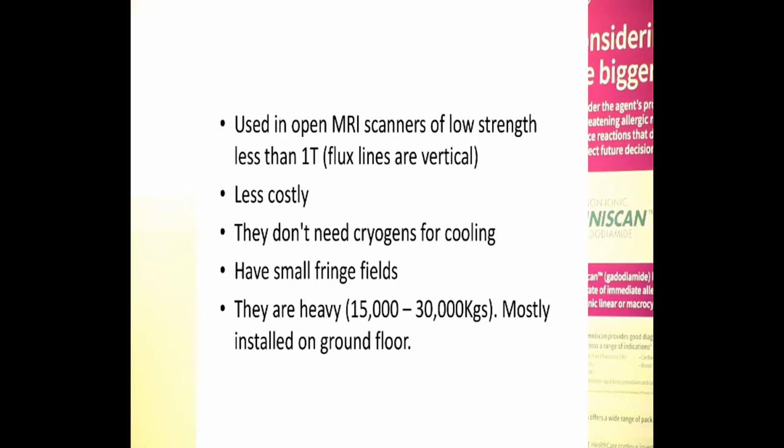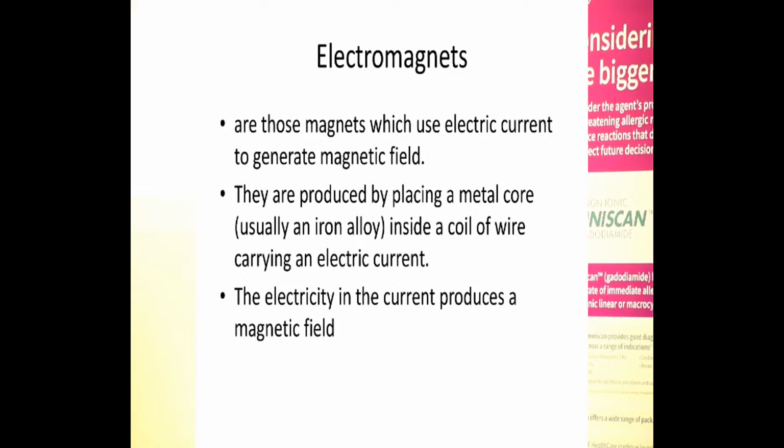They were used in early times, but nowadays they have gone out of market, and we have advanced to better magnetic materials. They do not need cryogen for cooling. We'll talk about cryogen in the next slide. And they have a very small fringe field, and they are very heavy. They range from 15,000 to 30,000 kgs, and they're mostly installed on the ground floor.